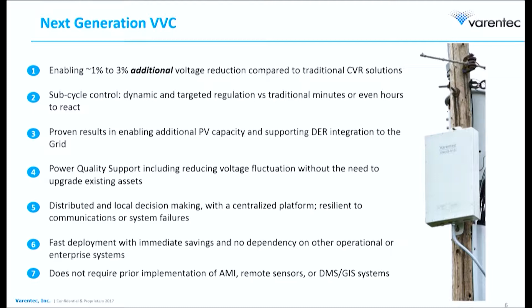The other point is the sub-cycle dynamic change. This power electronics monitors and controls, giving the end customer power quality despite changes or fluctuations in the loads. We've had projects where customers had a lot of voltage flickers because of different loads they live next to, and we were able to bring them within the 2.5% required in terms of flickering voltage on their end lines.